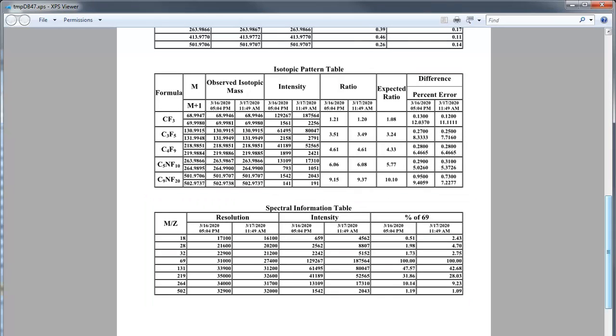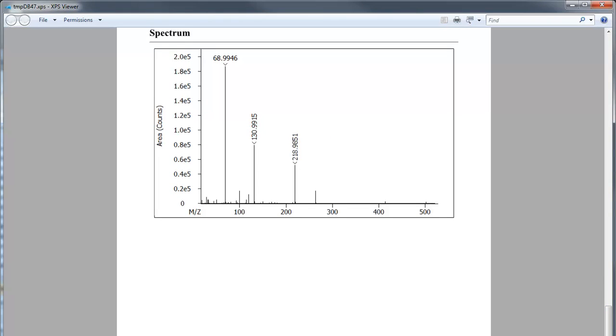The informational table shows the resolution, intensity, and percentage for specific air, water, and PFTBA fragment ions analyzed in this tune validation. It also shows the results from the last tune validation for comparison. The spectrum from the tune validation is displayed to visually show the air, water, PFTBA fragmentation, potential contaminants, and any other ionization fragments which may have occurred during analysis.